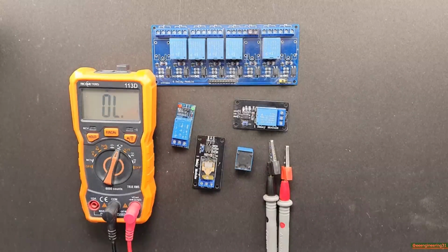If the diode is inside, you can replace the relay with a diodeless version as long as you add a diode outside. Just about any silicon diode will do. If the diode is already outside and all you have is a relay with a diode, you can use it. You don't even have to remove the extra diode on the board. Just be certain that the coil's connections are oriented so that the cathode of the diode connects to positive. Relays with diodes usually have plus and minus marked on their coil connections.